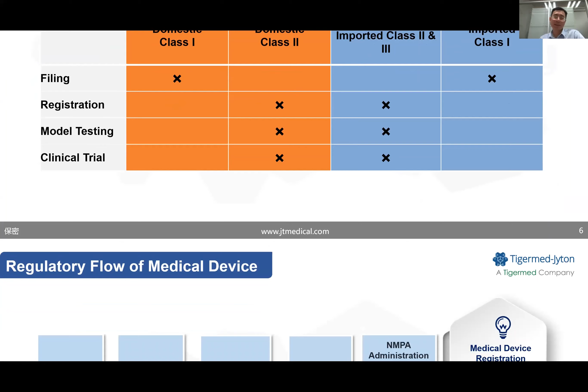The general steps for class 2 and 3 devices are like the following. We need to go first through a step called model testing. That's a registration test for the device itself. It's very much like a QC test according to national standards or industrial standards, to do some testing to demonstrate that the product is qualified according to all the quality standards or specifications the client claimed. And then you might need to do a clinical trial. Whether or not a trial is needed, we will talk about later.